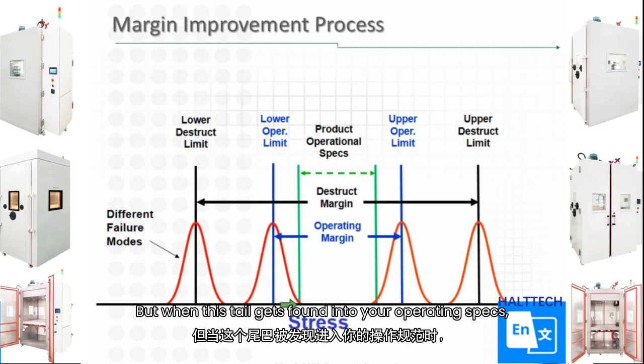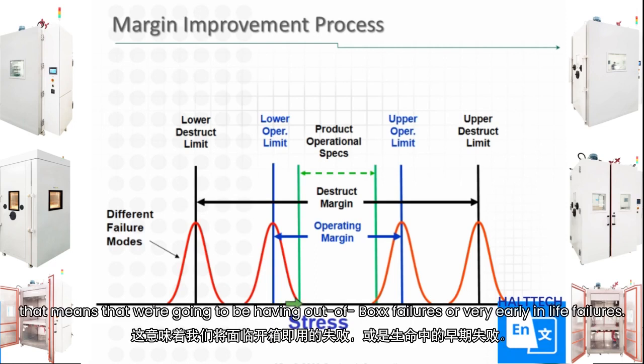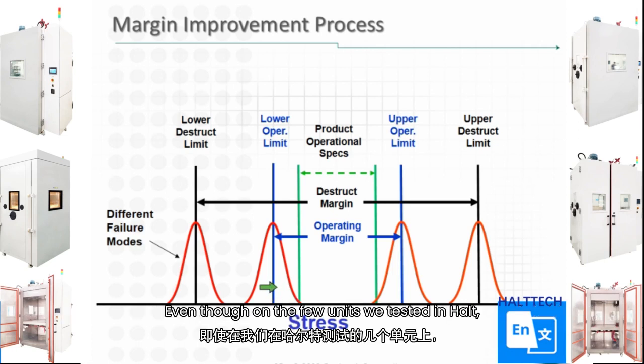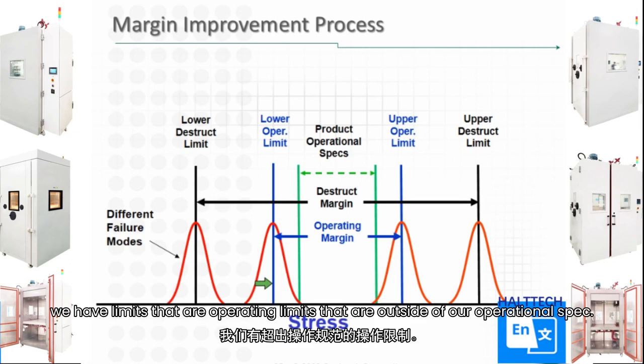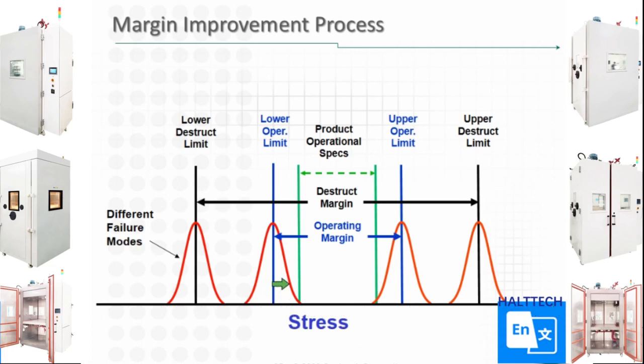But when this tail gets down into your operating specs, that means we're going to have out-of-box failures or very early life failures, even though on the few units we tested in HALT, we have operating limits that are outside of our operational specs.